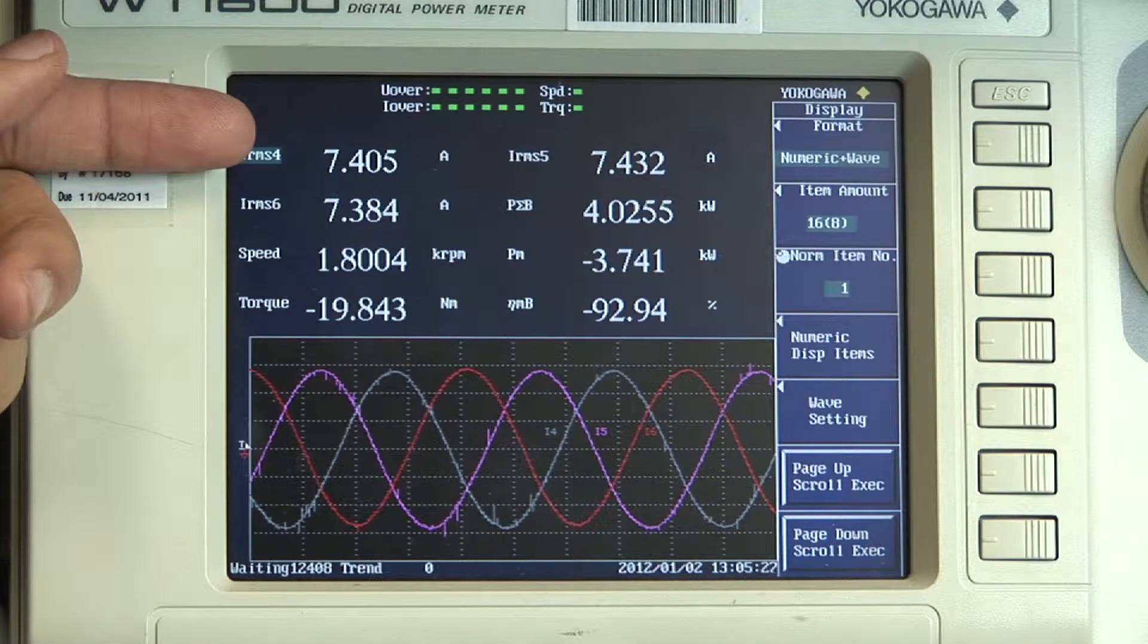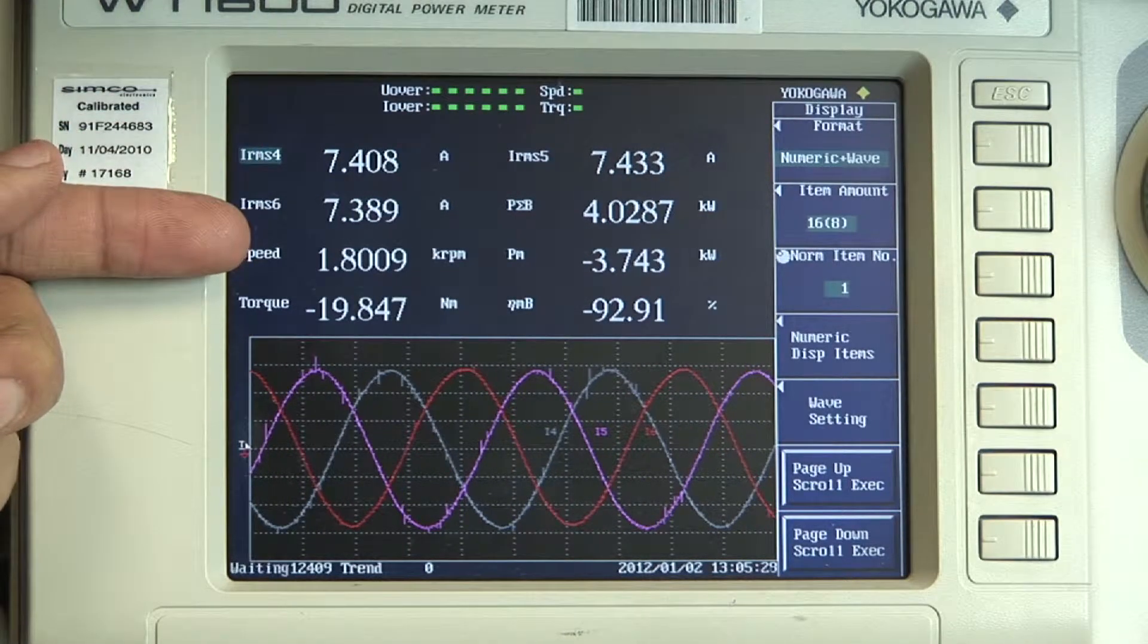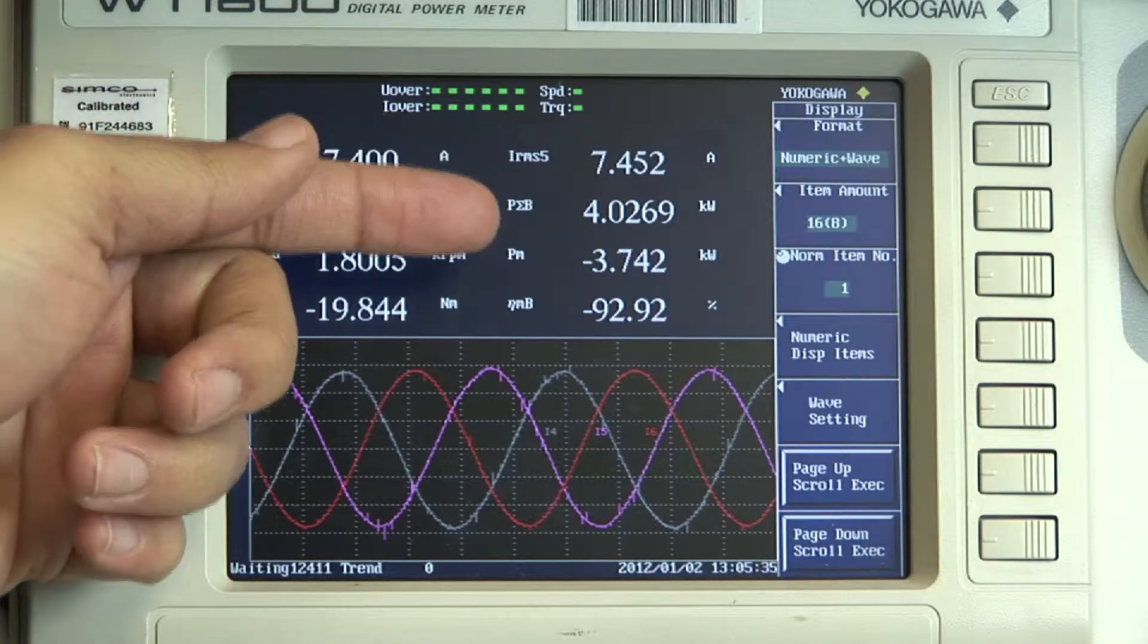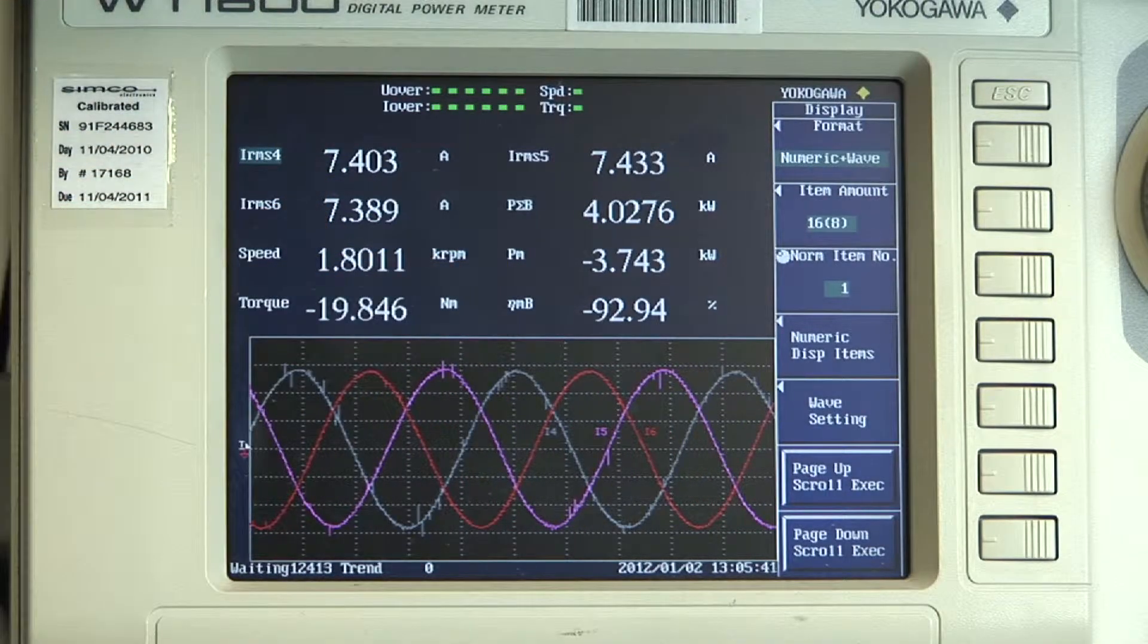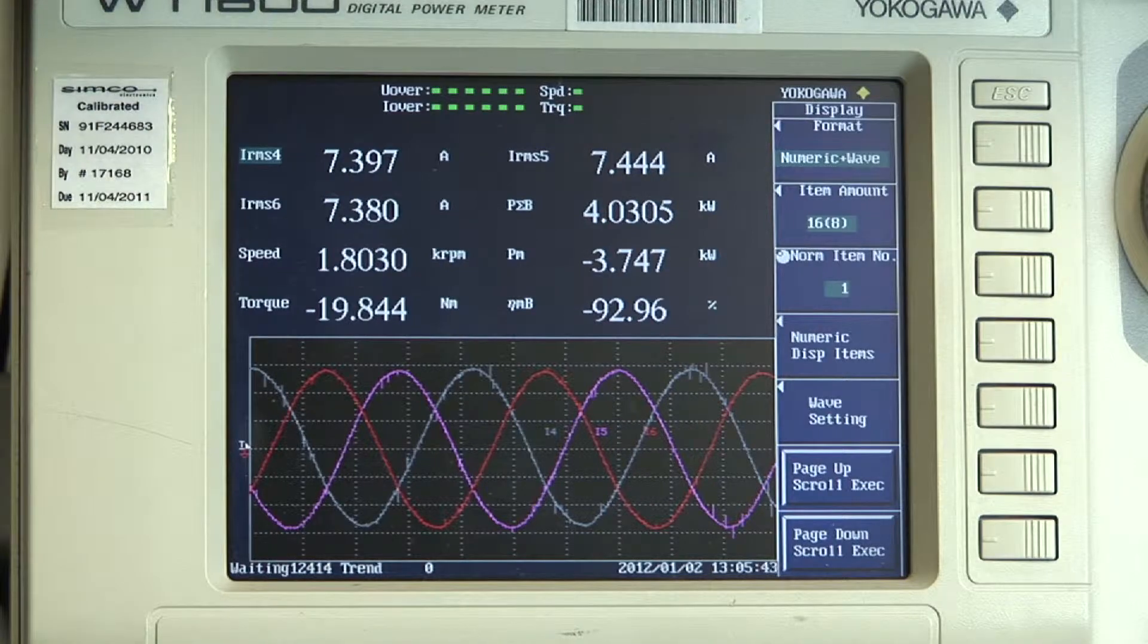On the power meter screen, we can see the values for motor current, motor speed, torque, motor input power, motor output power, and hence the resulting motor efficiency. We will now change the values for speed and torque to view the premium plus motor's performance over the operating range.